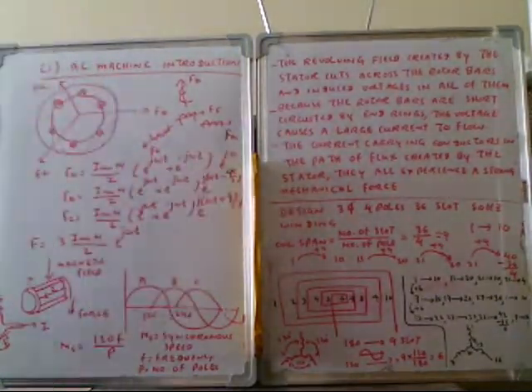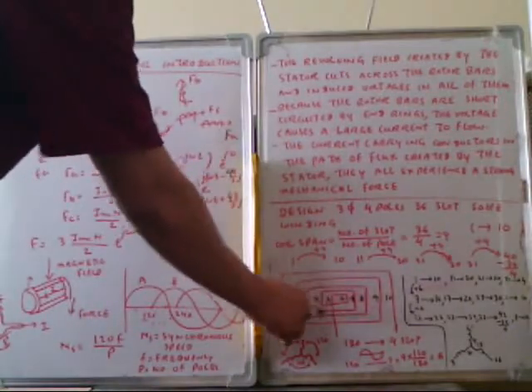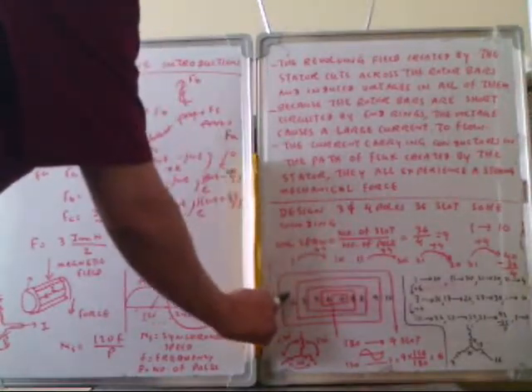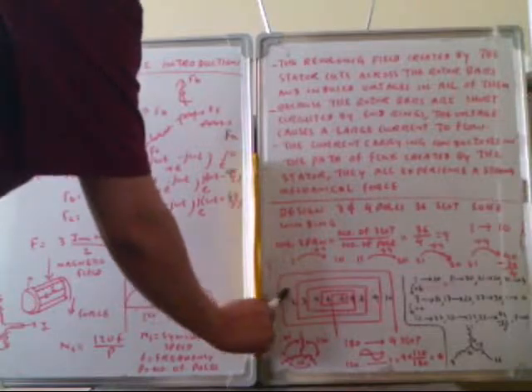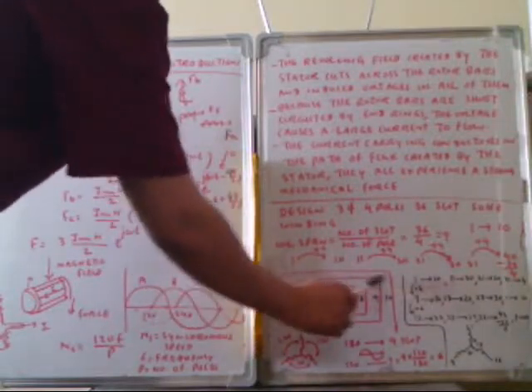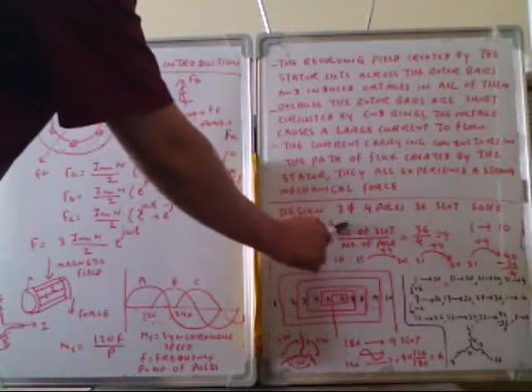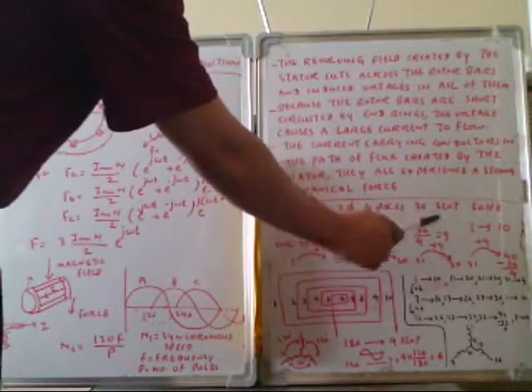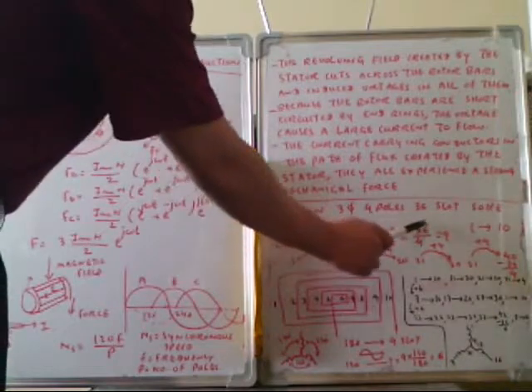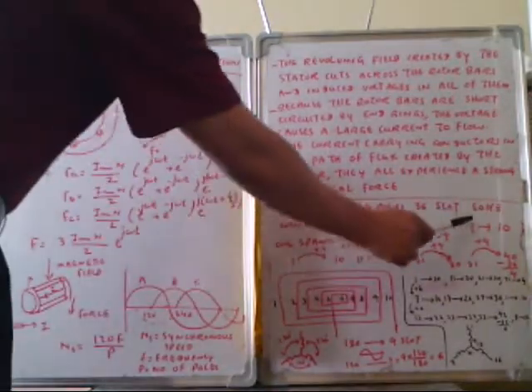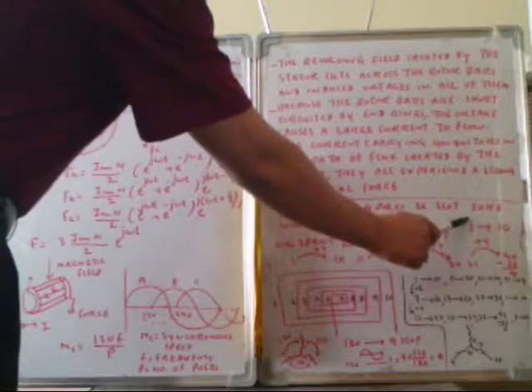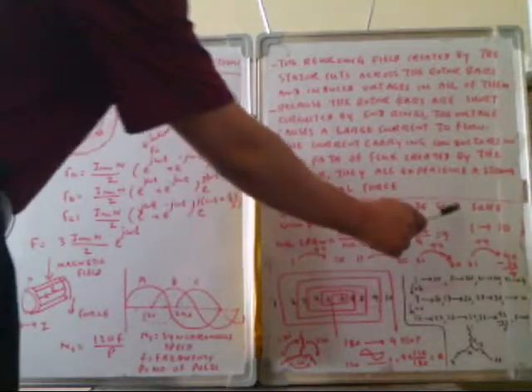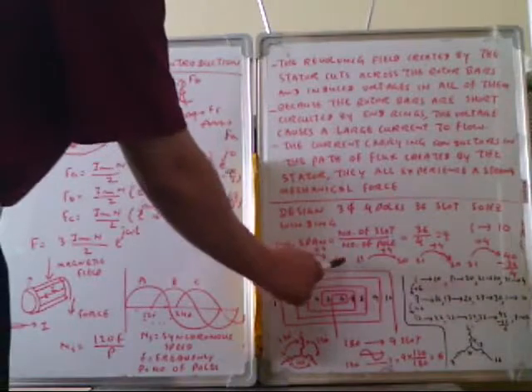Now see this problem. The stator has 4 poles, 36 slots, 50 hertz winding. When we are winding, this is one winding. How many slots will we take here? The span. We have to calculate number of slots by number of poles. So 36 slots divided by 4 poles equals 9. So the slot span is 9. We have to start from slot 1 and end at slot 10. So this is 1 to 10.